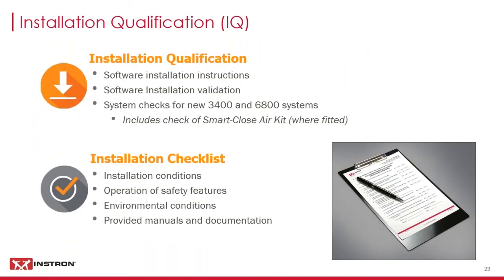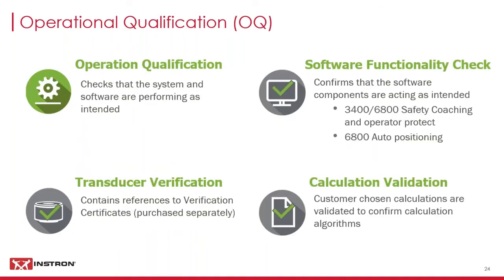As you might expect, an Instron IQOQ contains parts for both installation qualification, IQ, and operational qualification, OQ. The IQ confirms that the software and system is installed correctly. The IQ checklist includes items checked at frame installation, including installation of the software, frame safety features such as the emergency stop and travel limits, proper environmental conditions, and ensuring that the order is complete and that all parts and documents are provided. Our new 6800 and 3400 systems have additional checks, including Smart Close Air Kit functionality. The operational qualification, OQ, checks that the system and software are performing as expected.